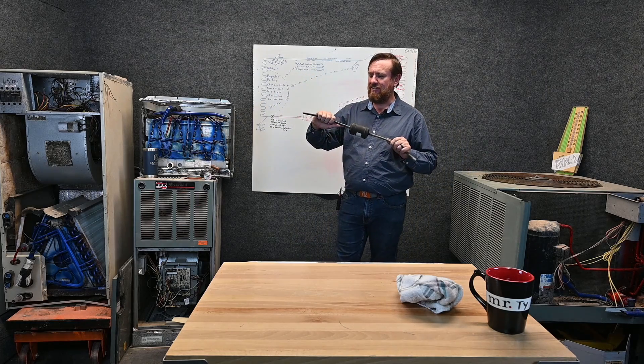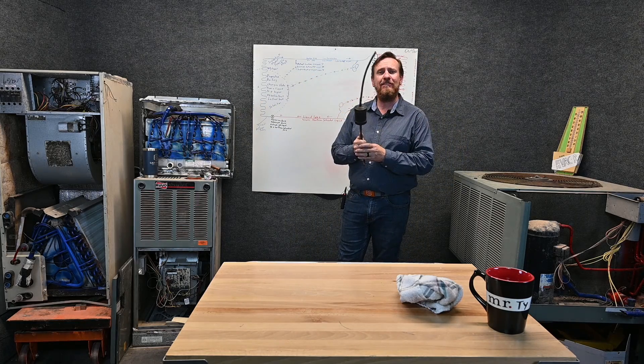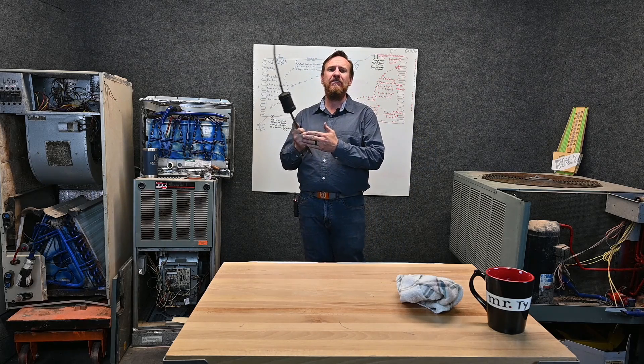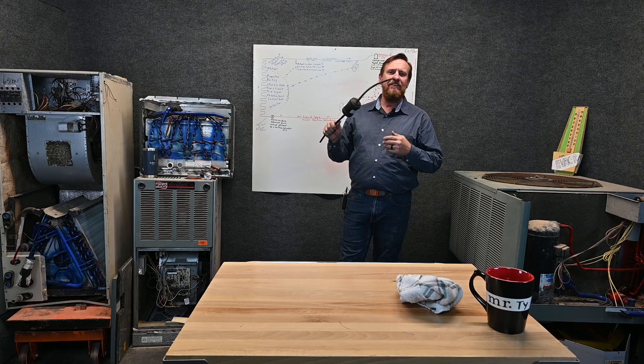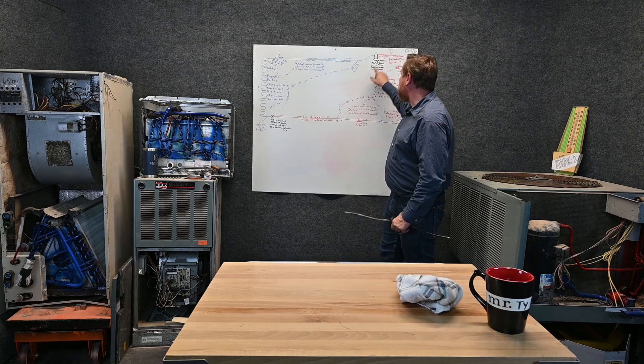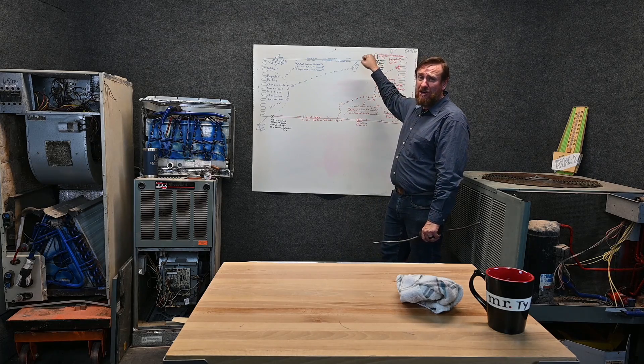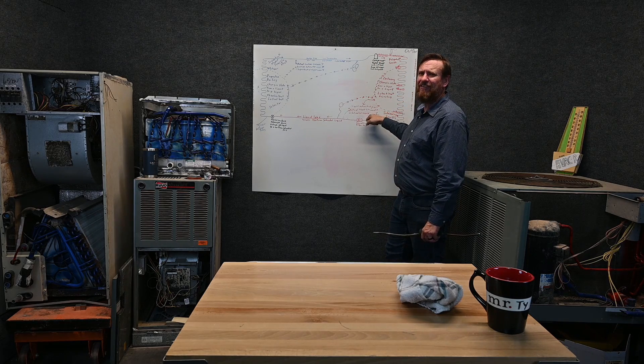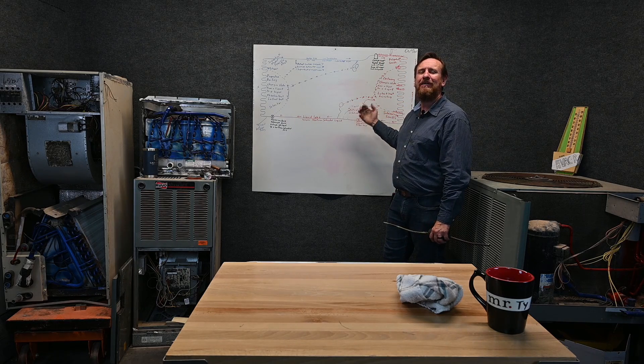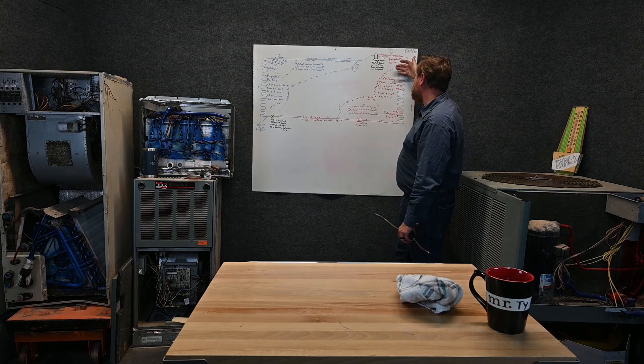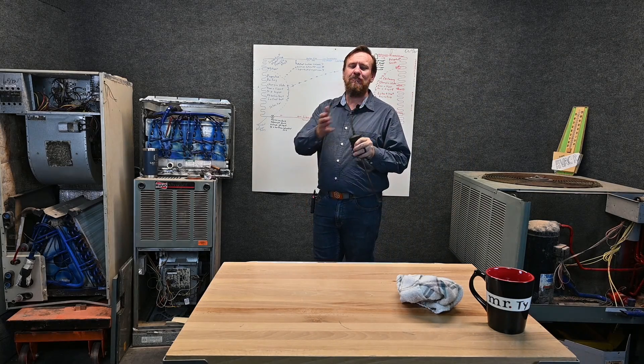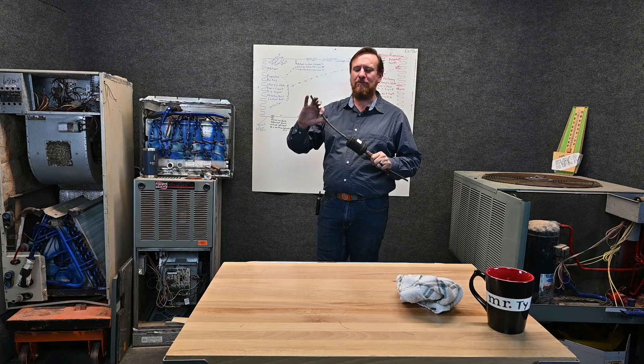Liquid refrigerant - you touch this it's going to be warmer than your hand temperature subcooled liquid so the heat leaving this line usually going into your hand. If you touch the line here it's going to burn you, will literally burn your hand, and then you get over here to this side you can feel the refrigerant is much cooler because it's subcooled liquid. Mainly because it changed state from vapor to liquid then we subcooled it below that liquid line and it's a small 3/8 line.